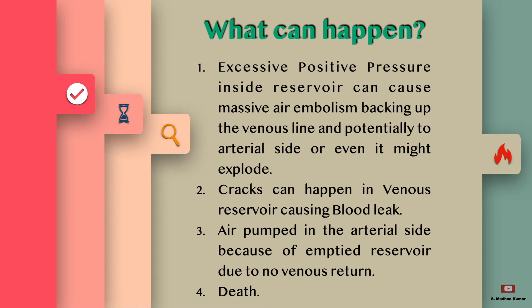In a worst-case scenario, it might get exploded also. Cracks can happen in the venous reservoir causing blood leak. Air can be pumped into the arterial side because of an emptied reservoir due to no venous return, and eventually it might end up in death.